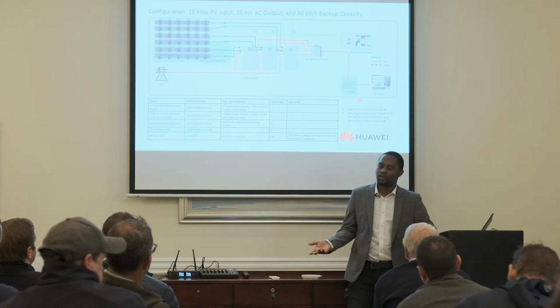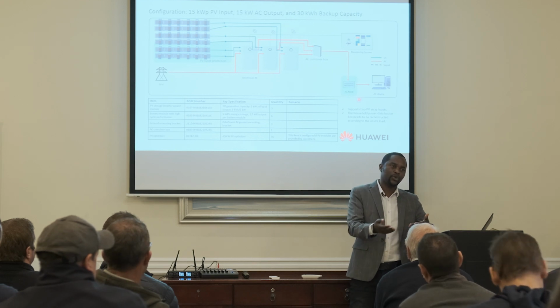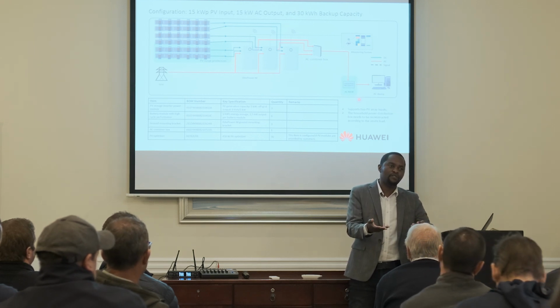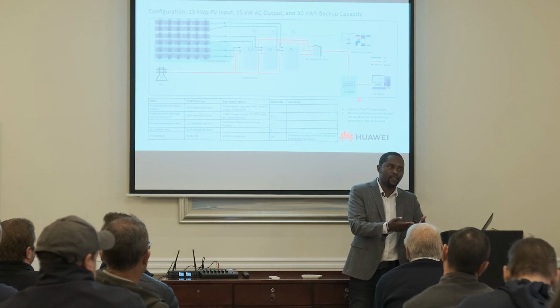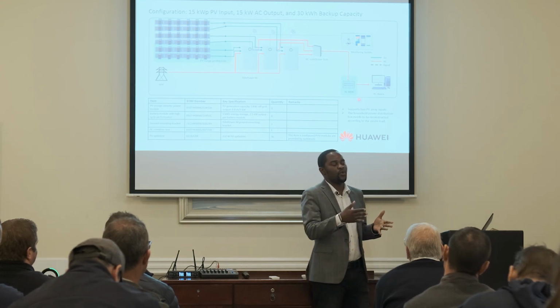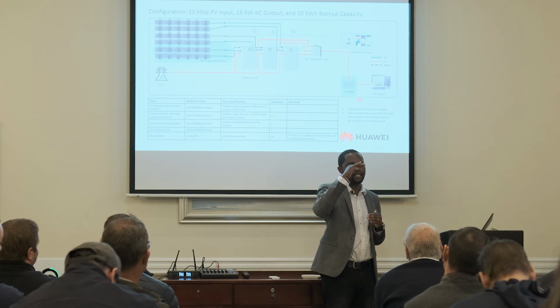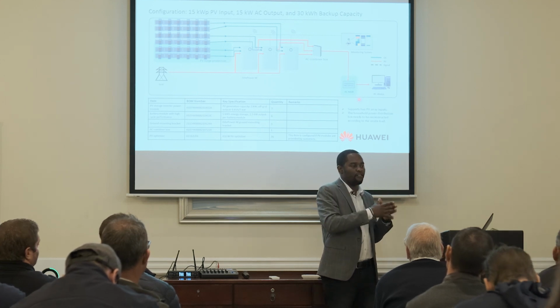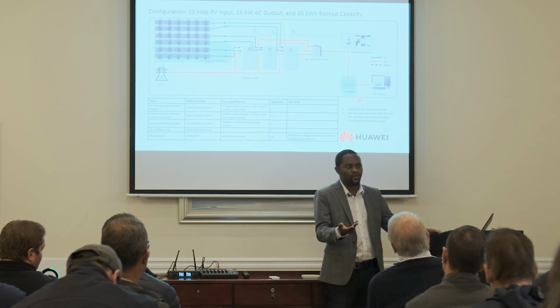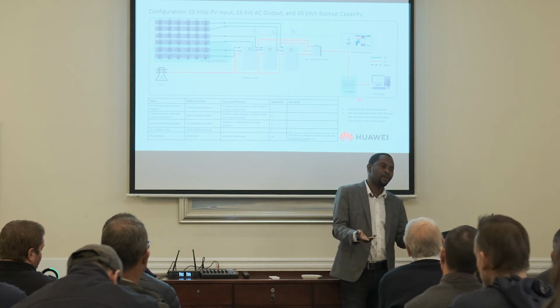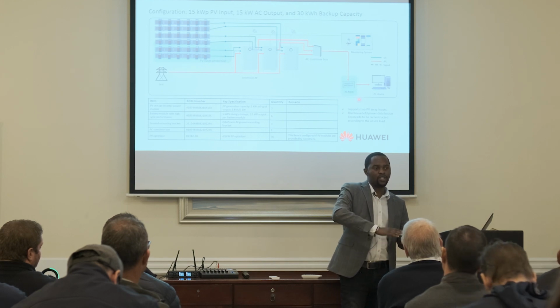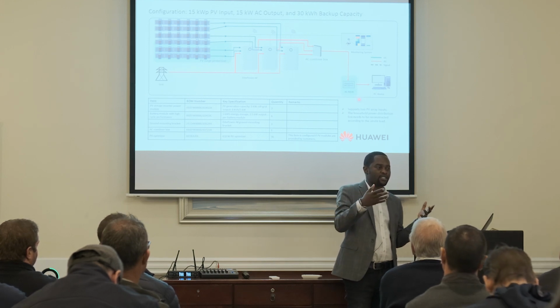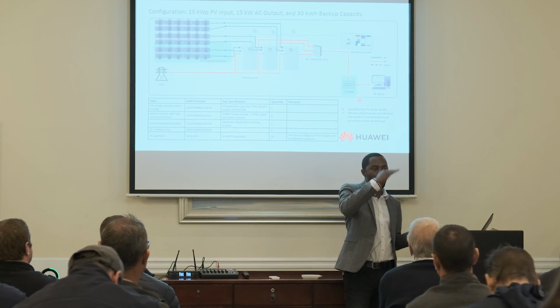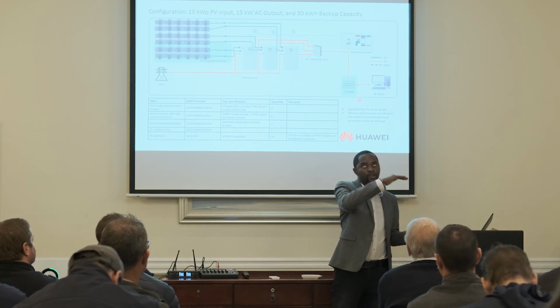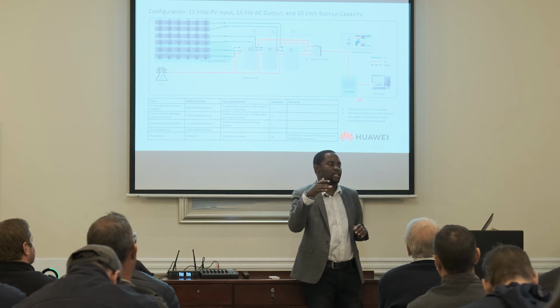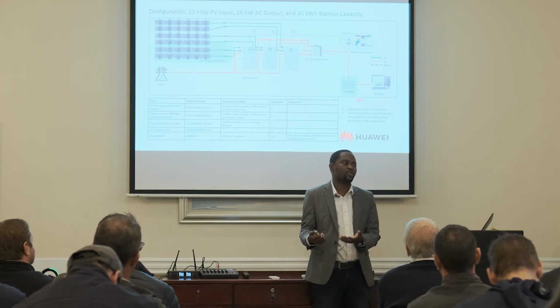But we've also realized that with load shedding, if you train your end user or just go and show your client, it's helpful for them to be able to change, especially the reserve SOC. In periods where you've got load shedding, you want that SOC to be up. You want at least enough reserve to cover you for the load shedding period. But in times when there's no load shedding, when Eskom is doing well, you may need to lower that reserve SOC so that you are allowing your system self-sufficiency. When you've charged your batteries, if you lower that reserve SOC, it means that when you've got a cloud or a bad solar day, instead of taking from the grid, you're actually discharging your batteries.